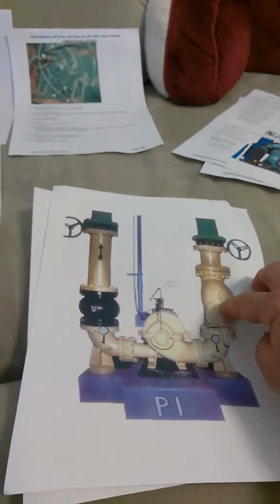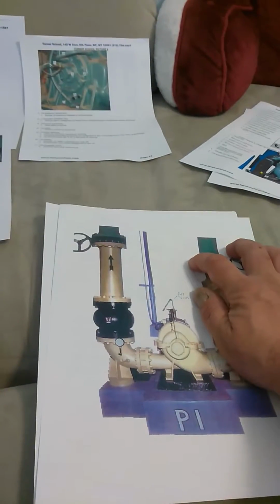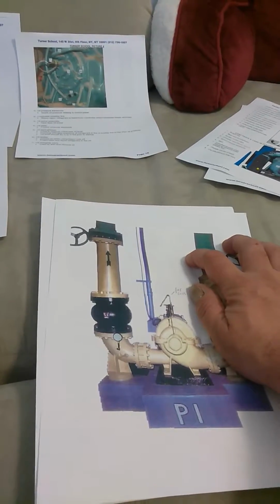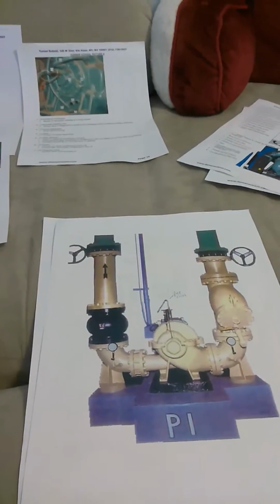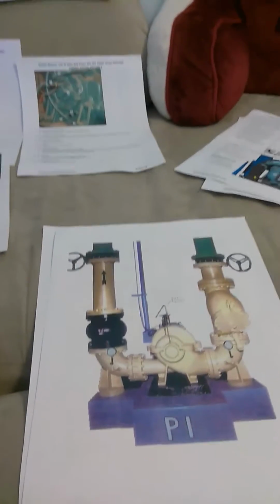You go to your chilled water pump. Check the strainer. Open the suction. Close the discharge valve. Put a disconnect on. Do the same thing. Then start compressor 1 and 2 on the back of the chiller and turn it on. Okay. Now we're going to do recovery again.